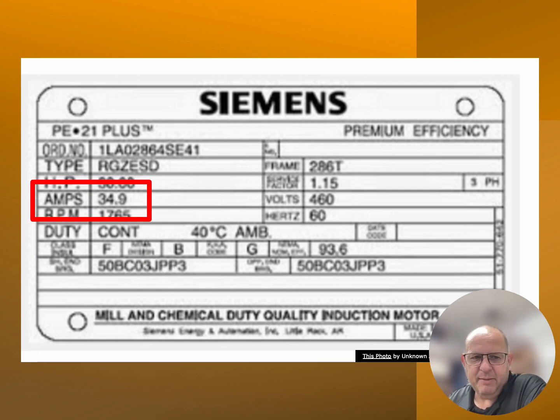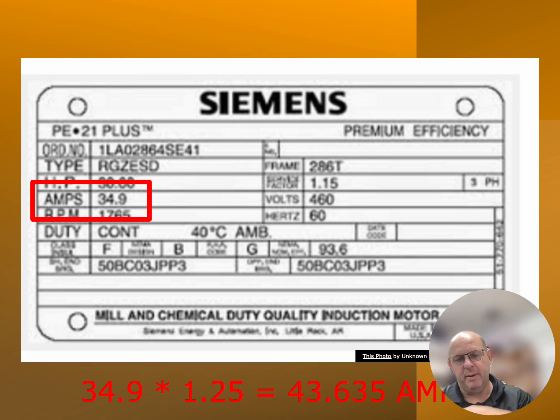So where do we find the amp draw? Right there. So take the amp draw of that unit, 34.9, and you're going to multiply it by 1.25. And you're going to end up with a breaker size, a maximum amp draw on this particular motor of 43.635 amps. Okay, let me back up here so that you guys can understand what's going on. This particular outdoor unit, motor, rooftop unit, it doesn't matter what it is.